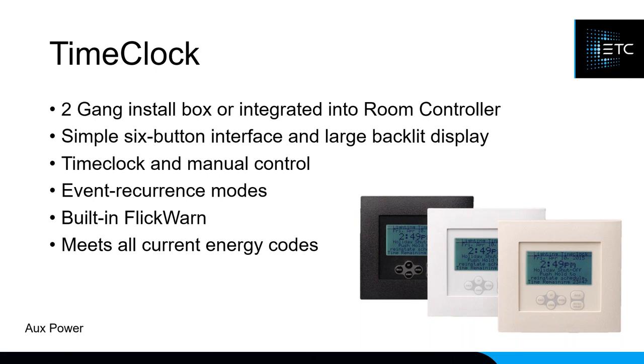One neat feature of the time clock is the built-in FlickWarn: about five or ten minutes before a timed event, all of your lights will flicker to show you what the next look will be. So if it's 9:55 and your lights are set to turn off at 10:00, the lights will flicker off to show you that in five minutes everything shuts off — giving you the chance to go back and override it if you'd like.